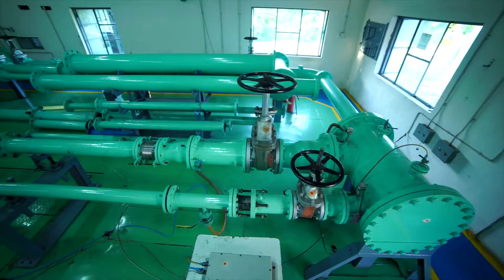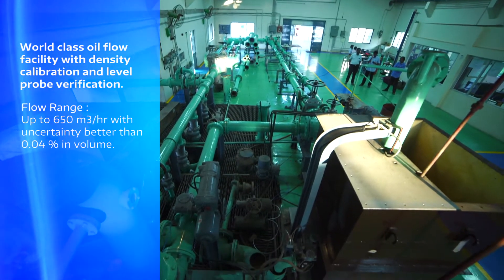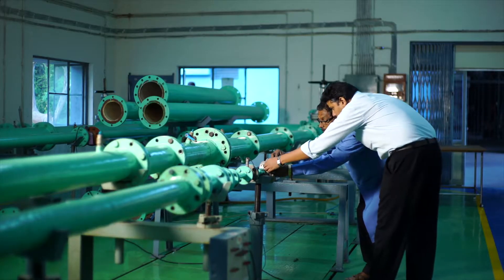The Oil Flow Lab at FCRI is a world-class facility designed for evaluation of flow products in oil media. The facility has a flow range up to 650 cubic meters per hour with uncertainty better than 0.04% in volume.